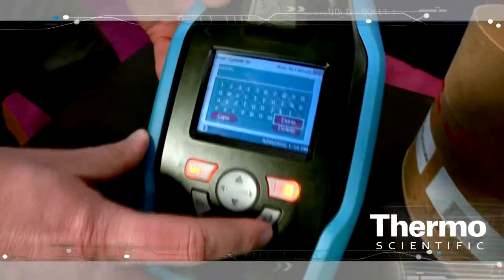Tell us about the ease of use and what they can really do with it. The instrument is designed to be used by a layperson, someone down on the dock, who doesn't have a spectroscopist background. What we've done is simplified the user interface, so they run a sample and can barcode in the method ID they want to run, the LIMS number, the SAP number.